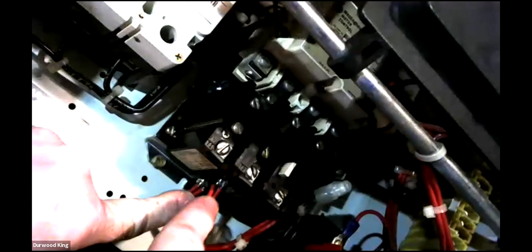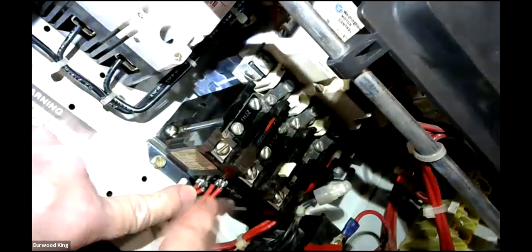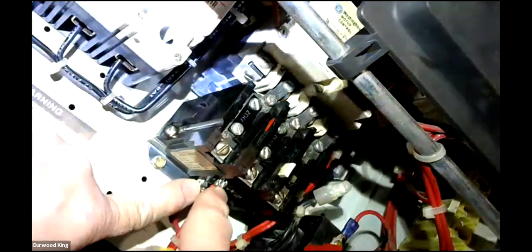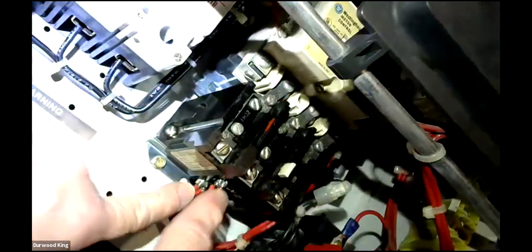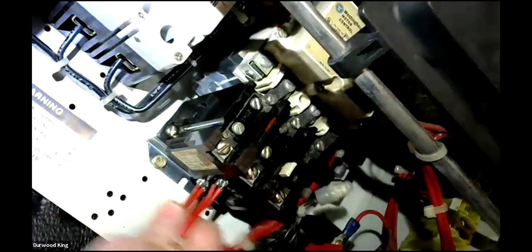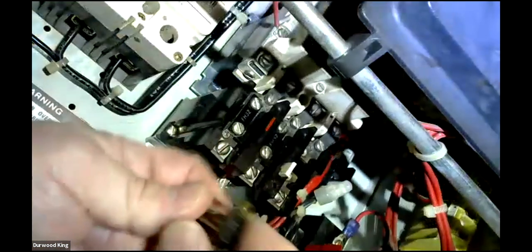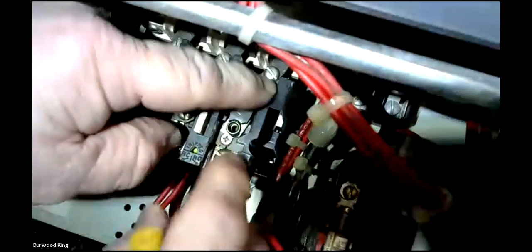These two wires down here, that normally closed contact's going to pop open. So that is your normally closed that's actually tied to your coil. This actually will disengage the coil if it pops open. And the way you can test that, if you wanted to test it, well, let's go back in with this thing first. So you just drop it in the hole like that, and put your screws in.